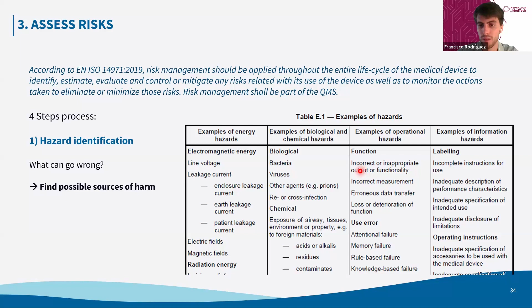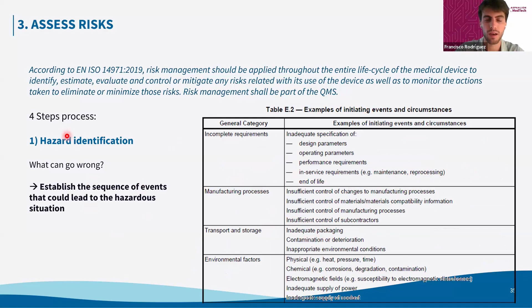The first step is the identification of the hazards, okay? This includes defining the possible sources of hazards, for example biological contamination, energy hazards, use errors, etc., and also the hazard situation, meaning the sequence of events that needs to occur between a hazard and a risk arising. For example, there could be a hazard which is biological contamination, but it won't be a problem if we have adequate packaging. So the hazard situation would be that we don't have adequate packaging, so the hazard of biological contamination appears, okay? This is the hazard identification phase.